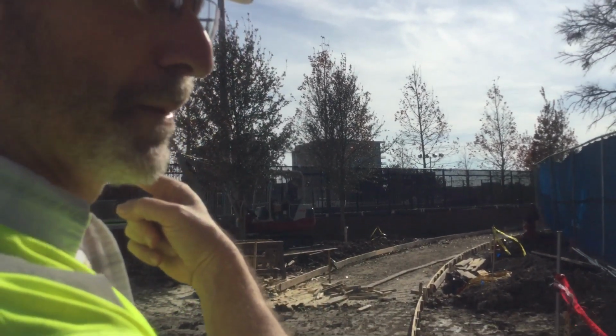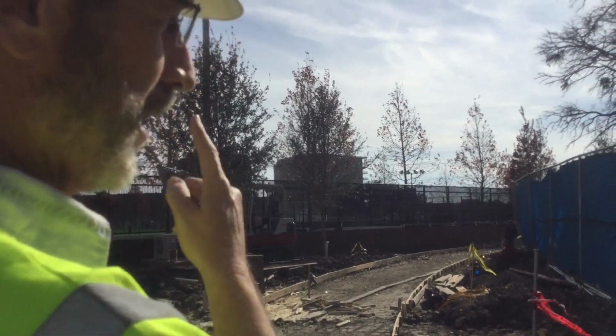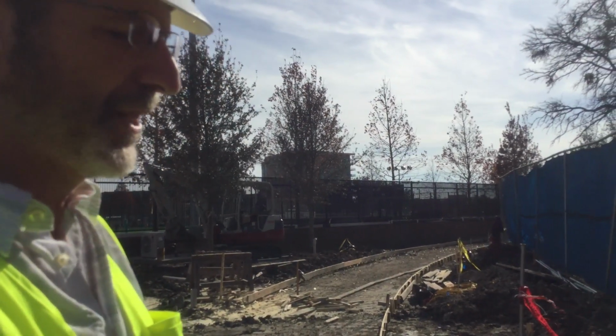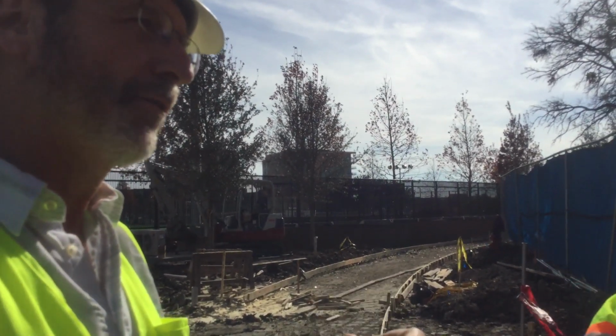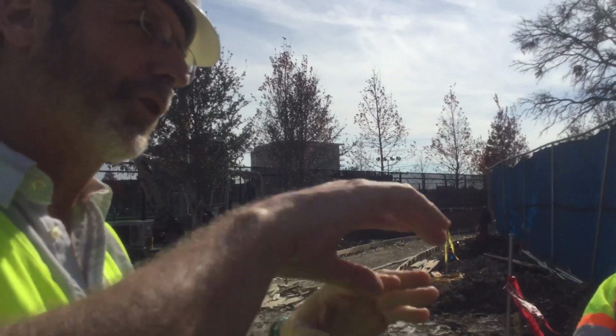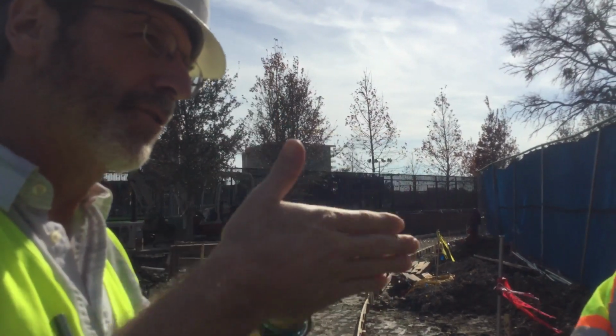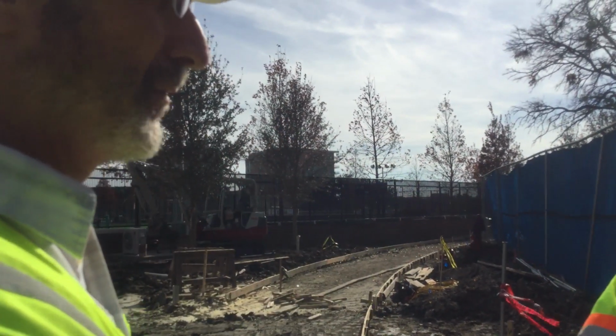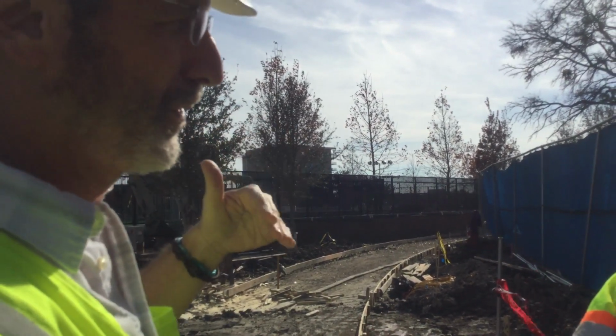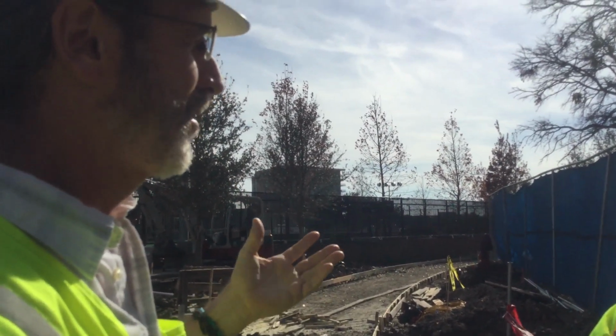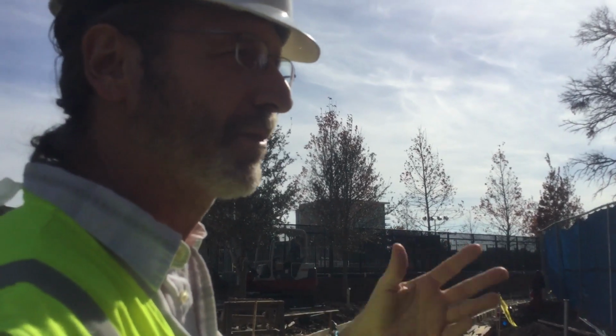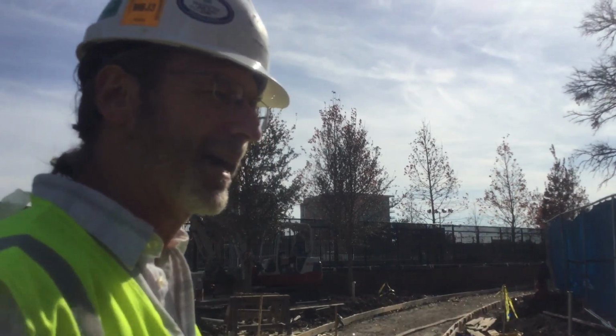There's 2 photo cells on this building. One is for this system, the other is for the court lighting. It's got a little movable sleeve over the movable plate that goes over the eye. That's how you determine your bright-dark setting. It's looking north, so it ought to be fine, but if you discover it's turning on or off too bright or too dark based on sunrise/sunset, you can tweak that.